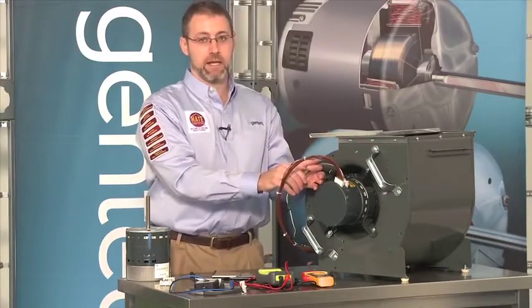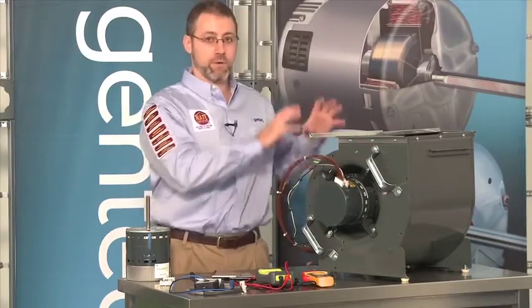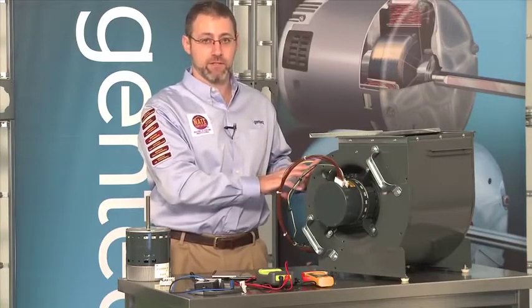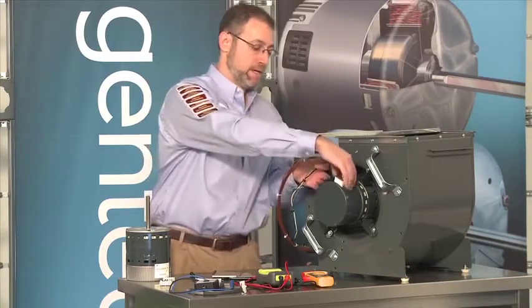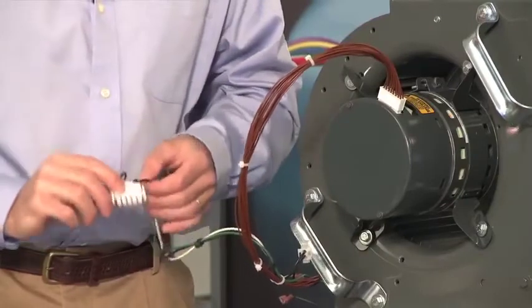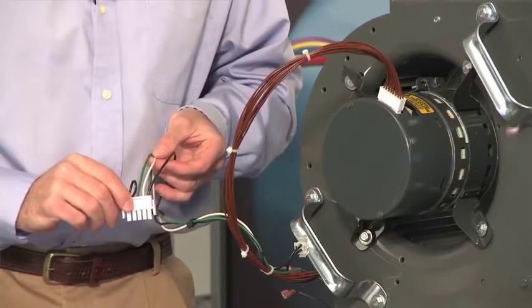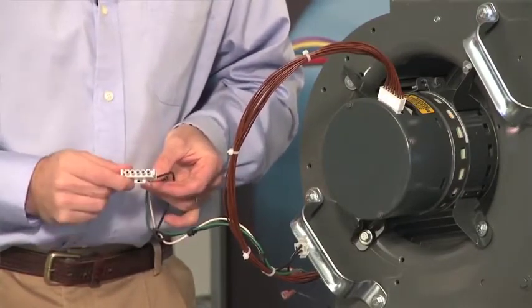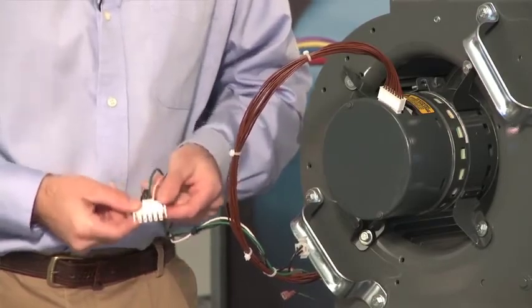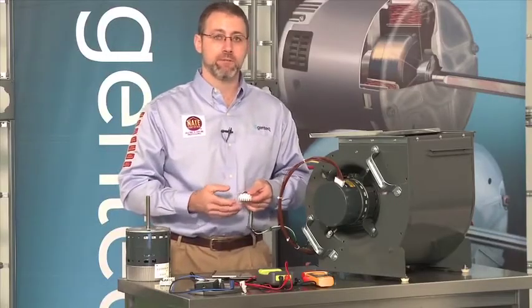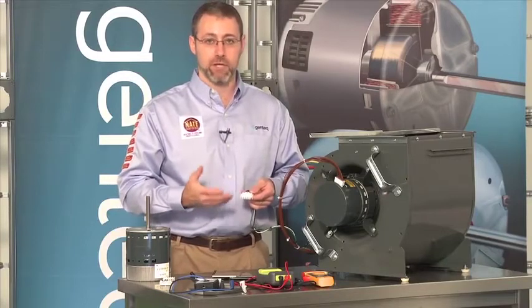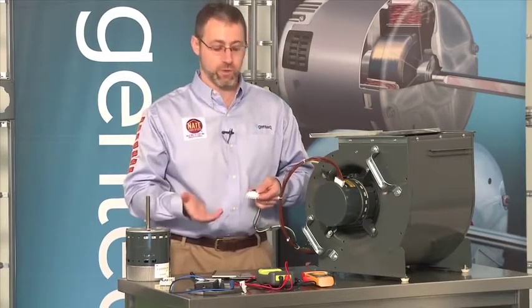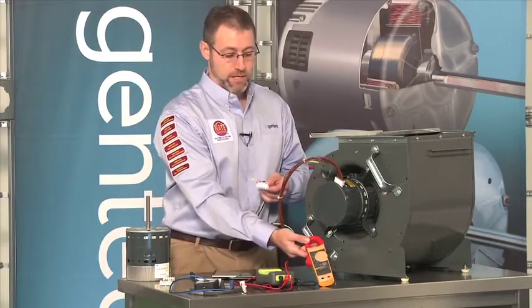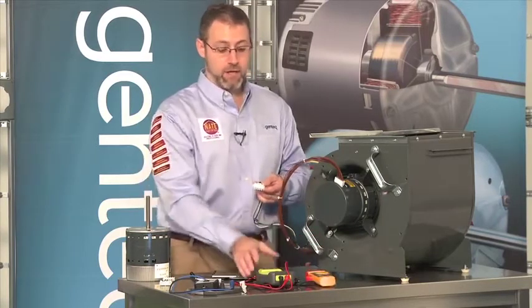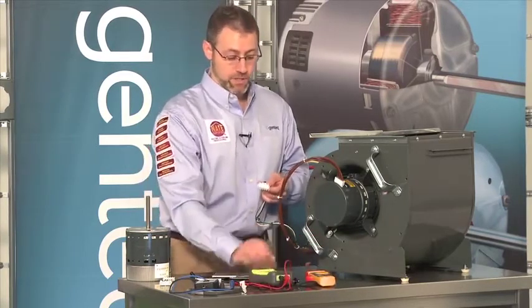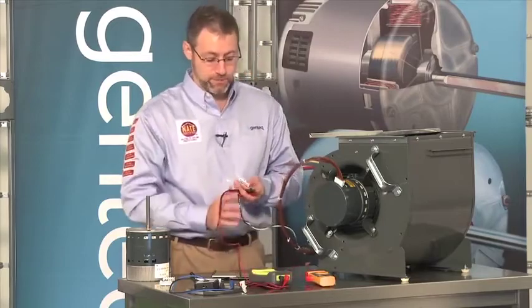Before we would disconnect any of our plugs, we would want to turn the power off on our HVAC system. So I've turned the power off, and I'm going to now disconnect my plug, and then I'm going to turn the power back on my HVAC system so I can check the voltage on this plug. And the voltage on this plug is going to be the same as what's driving the HVAC system, either 120 or 240. And you can use any clamp-on, digital, or even analog voltmeter. We're just going to use a simple digital voltmeter here.